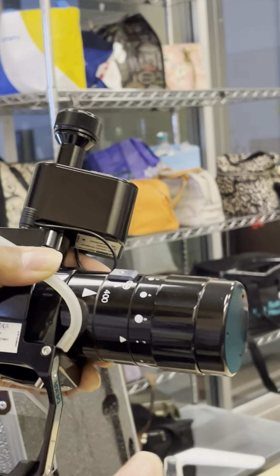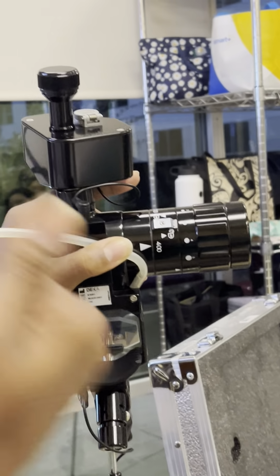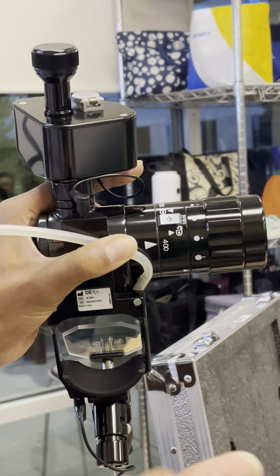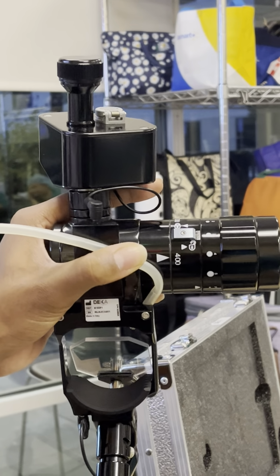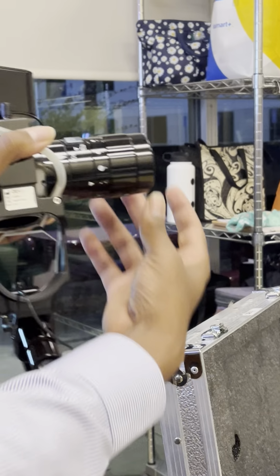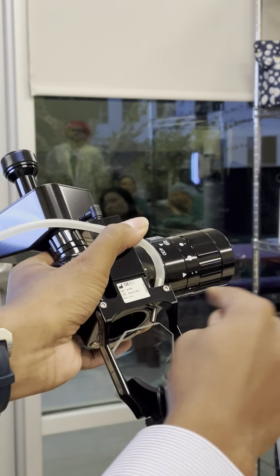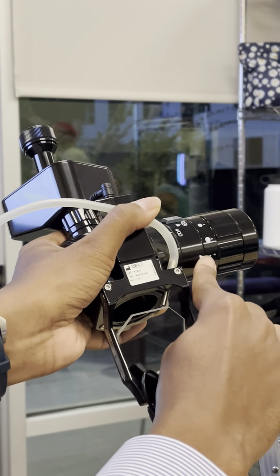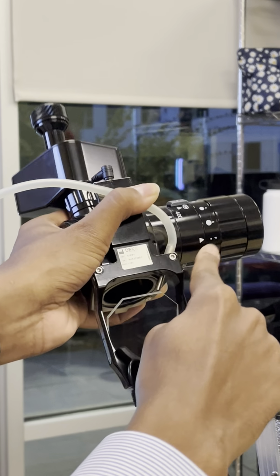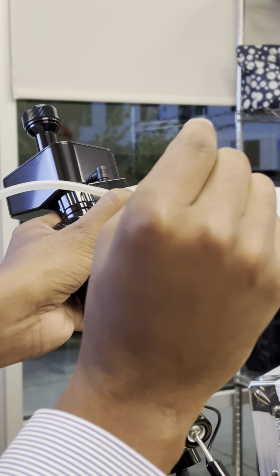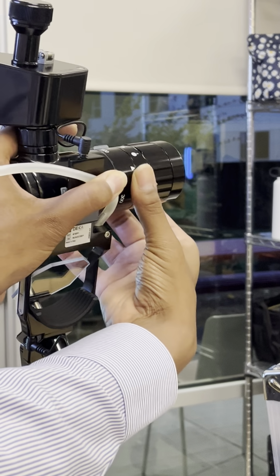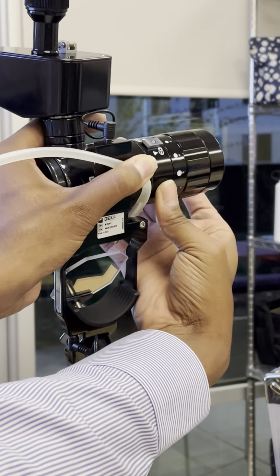I'm going to say it one more time because it can be a little bit confusing. 400 is typically the working distance for direct laryngoscopies, under microscope, or microlaryngoscopies, direct suspension. In order to get it to 400, you have to unlock it by being in fine focus. That's the smallest point that the Microman can make. That allows you to move the entire wheel.